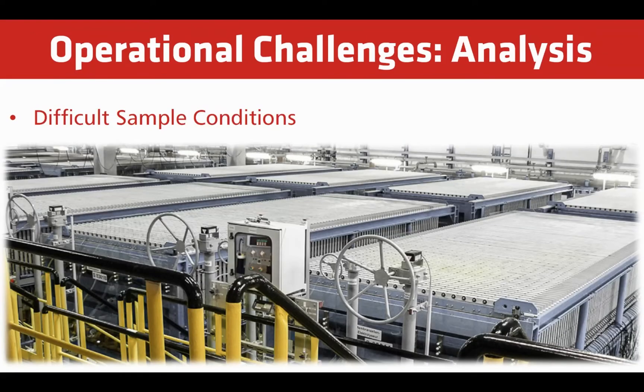Protecting the membrane cell is of utmost importance. However, the saturated brine sample is very difficult to handle for online monitoring. Cooling hot brine causes scaling in fluidic systems, which increases hands-on maintenance time. How are you currently controlling caustic dosing for optimal precipitation? Are you relying on inline pH sensors or performing a true acid-base titration for tighter control? How are you monitoring low ppb concentrations of hardness, and does your analyzer always detect upsets?